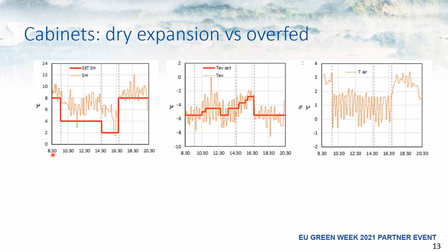The interesting thing is that as soon as we decrease the superheat, we can see that the temperature of the air inside the cabinet drops. It drops from 3 degrees down to 1 degree. So the system is performing much better. And it's performing better with a low superheat even if we increase the evaporation temperature. So by decreasing the superheat, we are able to increase the evaporation temperature and still get a better performance.